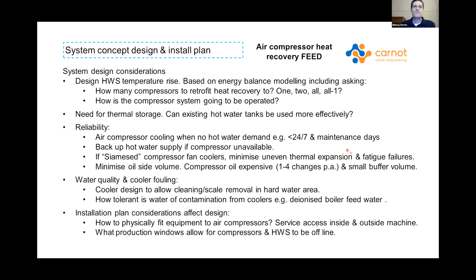So some of the design considerations from that: hot water system temperature rise, what do you actually need the hot water for? Are you going to fit heat recovery to all of your compressors or to one of them, or to one of them minus your standby machine? Because often you'll have at least a standby machine in your compressed air plant. And as we've talked about, how are you going to operate your air compressor system? If you're only doing a reduced number of coolers, you have to optimize what machines you run so you can recover as much heat as you can. There's no point operating one machine that hasn't got heat recovery on it, because you've just wasted your investment. Need for thermal storage. And then we get into the fun topics, which some of the other presenters have talked about, which is the reliability and water quality factors, and how you design the system around that.